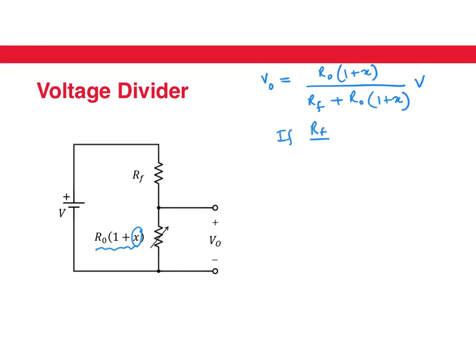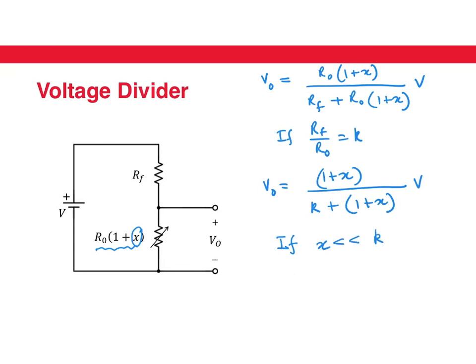If RF over R0 is equal to K, we can rewrite this equation. And if we assume that X, our fractional change in resistance, is much less than K, we can write V_output in a simplified form. We can write it as (1 + X) and essentially ignore X in the denominator because it's much smaller than K, giving us V/(1 + K) plus X/(1 + K) times V.